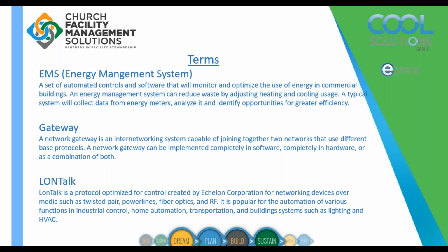Gateways, as we start bringing in Wi-Fi stats, smart building controls, all this digital stuff, you need to make sure all the different systems can communicate. Many times you may have to look at installing a gateway to provide that bridge between different systems. Some can be set on your server or your internal network, but sometimes you've got to provide a gateway to translate between one programming type language to another. LonTalk is similar to BACnet in that it is a standardized programming and communication protocol.